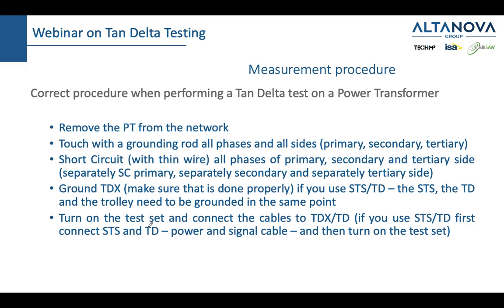Sometimes people forget to execute that step, and if that step is not executed, therein lies the risk of damaging the testing equipment. So the thing is that you should take your grounding rod and touch all phases of primary, secondary, and if you have a tertiary side, with the grounding rod, thus de-energizing fully the transformer. The transformer needs to be fully de-energized, because if it's not, some remaining current or voltage can close itself through the measurement of the tan delta device. And this is something which can then damage the testing equipment.